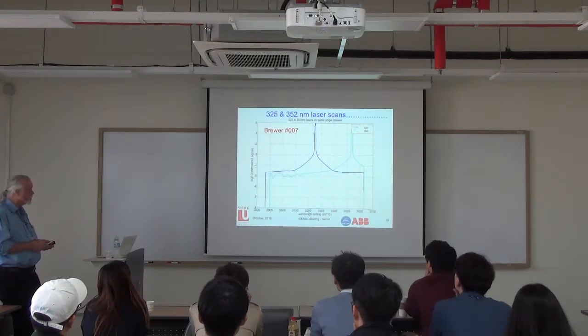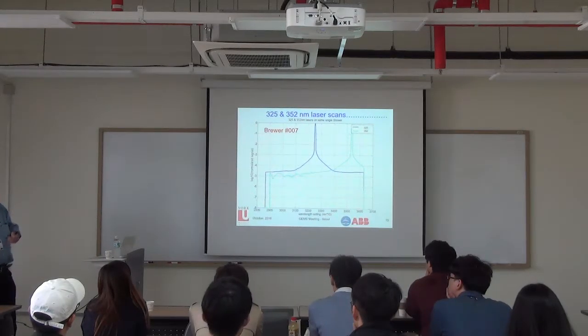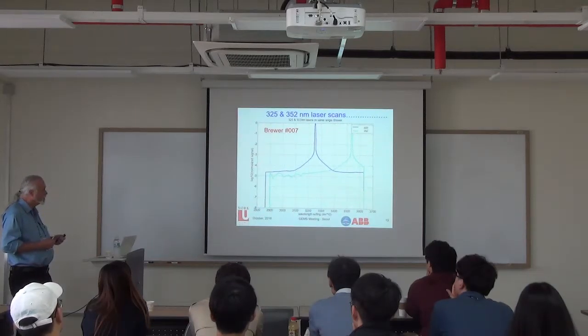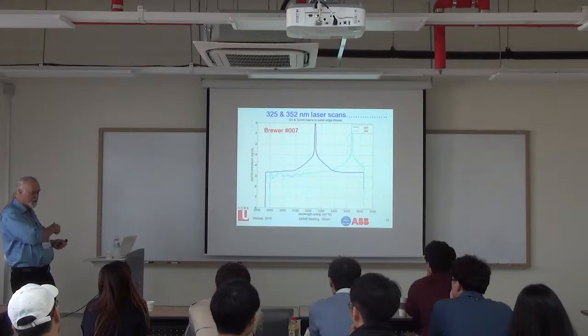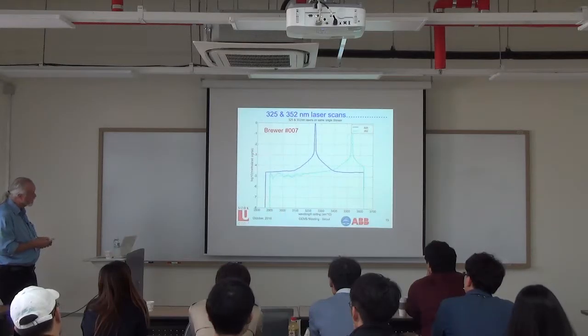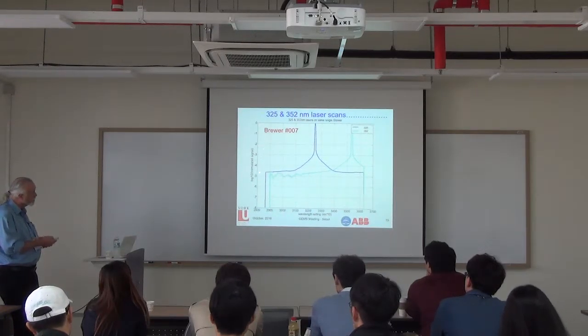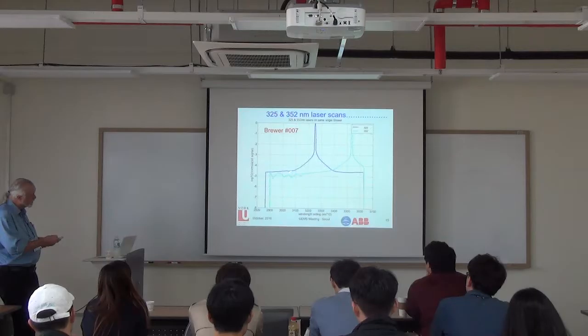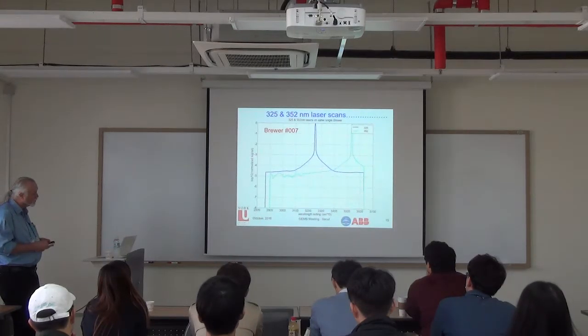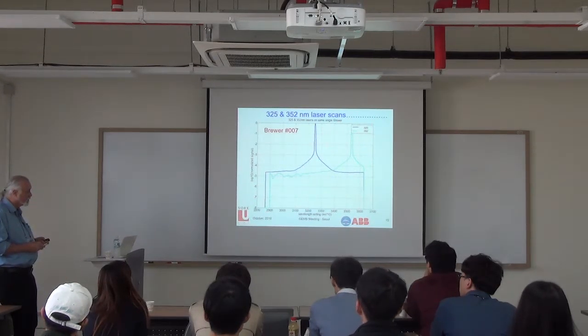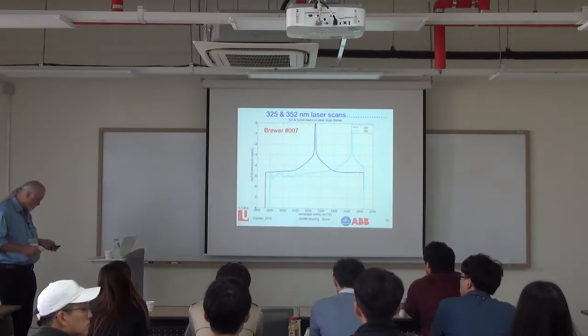Brewer No. 7 is a single monochromator—one diffraction grating, one entrance slit, one mirror, exit slits, and a photomultiplier detector. It's more susceptible to stray light than a double monochromator, where light passes through a second instrument to reject stray light. The gratings are really quite good, but there is an area of local stray light that is quite important because the gradient of ozone absorption is so high. It's the nearby stray light that is more important than light from far away.